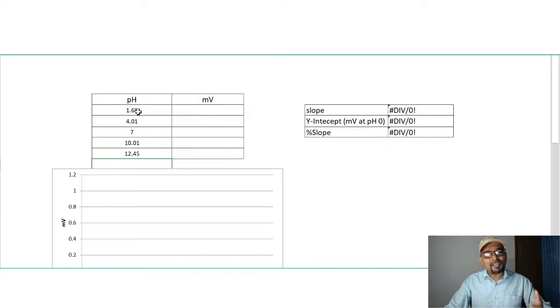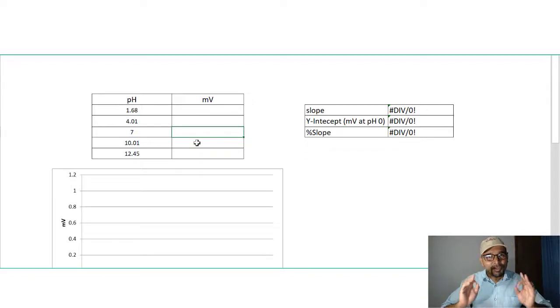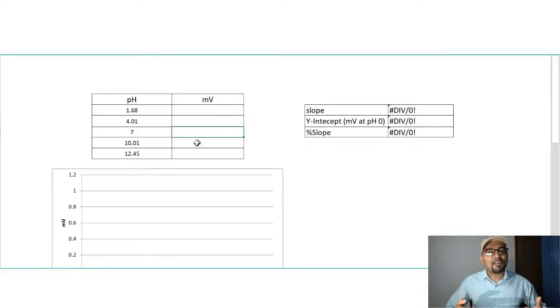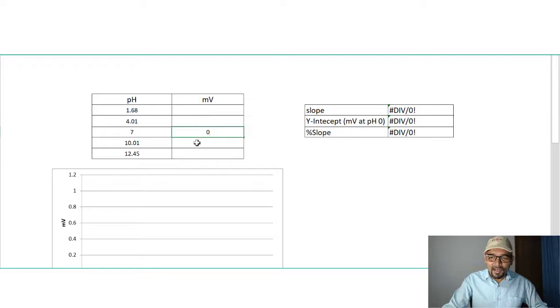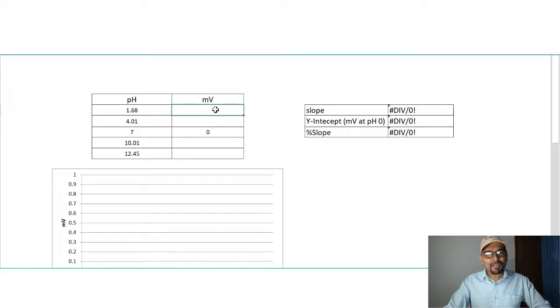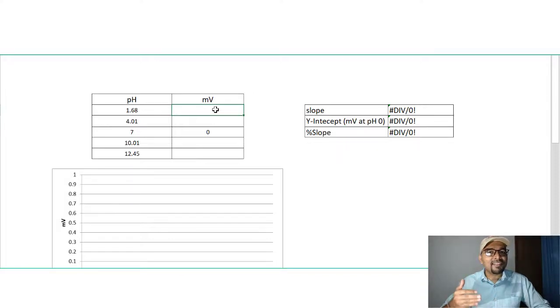What should be the potential value at pH 7, where pH is neutral? At pH 7, there is no transfer of ions across the glass membrane, so the expected potential should be 0 millivolts. Ideally, at pH 7 you must get a potential of 0 millivolts. Now, what should be the potential at pH 1.68? Recall that for each 1 pH unit, there is a change of 59.16 millivolts.